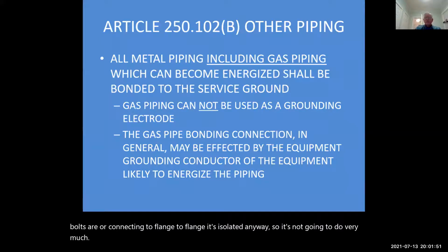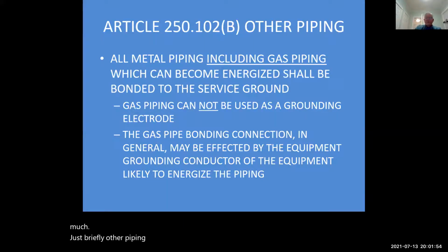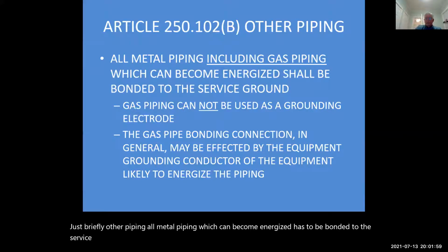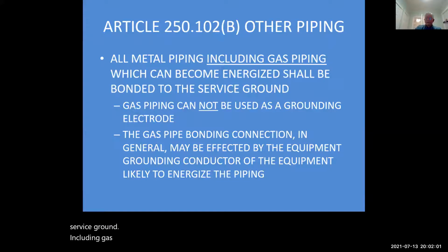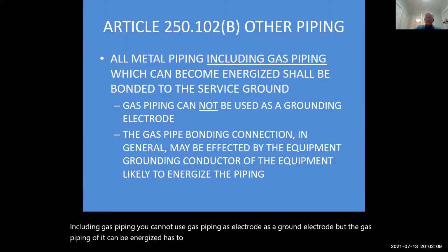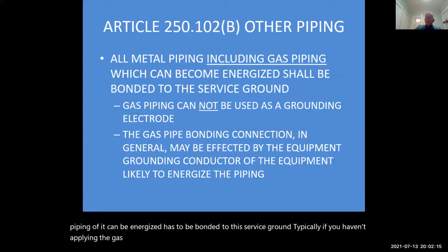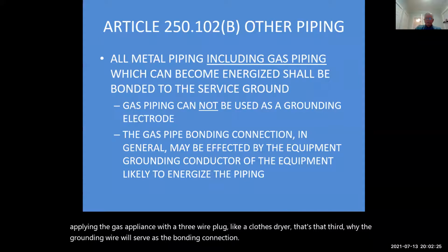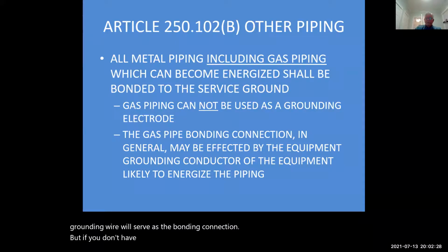Just briefly, other piping, all metal piping which can become energized, has to be bonded to the service ground, including gas piping. You cannot use gas piping as a ground electrode, but the gas piping, if it can be energized, has to be bonded to the service ground. Typically, if you have a gas appliance with a 3-wire plug, like a clothes dryer, that third wire, the grounding wire, will serve as the bonding connection. But if you don't have that, then you would have to have a bonding conductor.